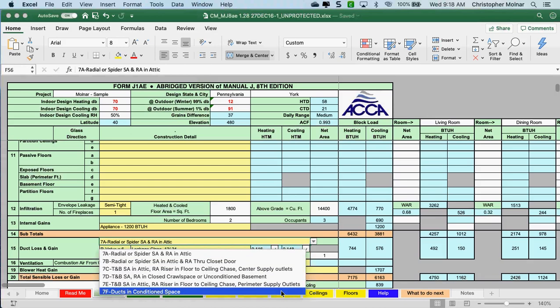For anybody else on a two-story building, you have to figure out where you can run ductwork. If it's new construction, you can run your second floor ductwork through the floor joists and use floor registers. If you're putting air conditioning into existing construction, you really can't get into the floor joists without doing major ceiling damage, so you almost have to get the ductwork into the attic and come across, or use chases, or use two systems.